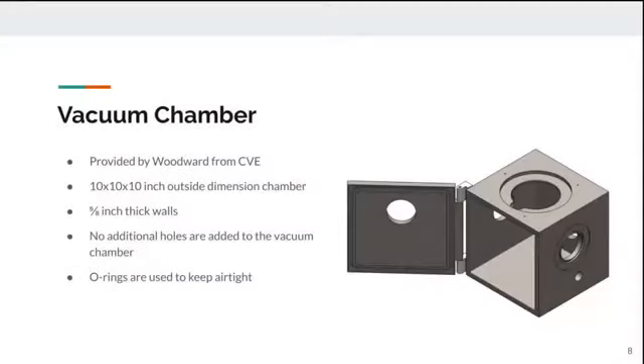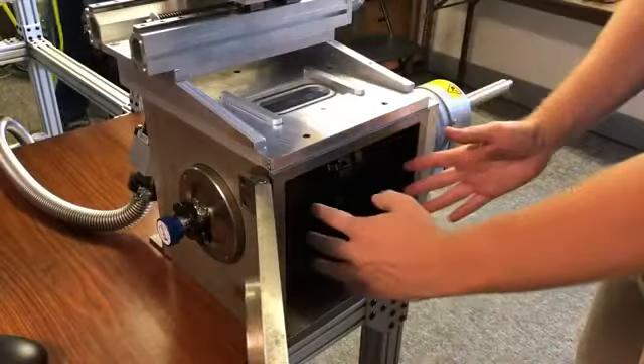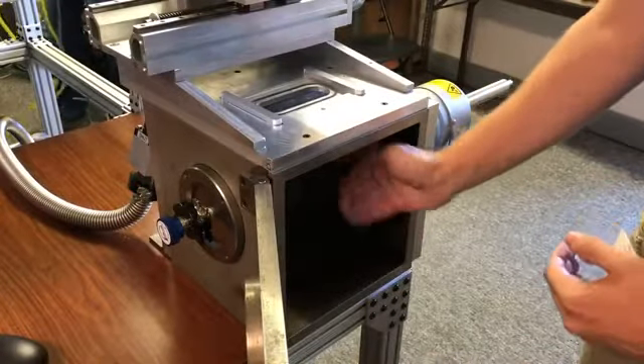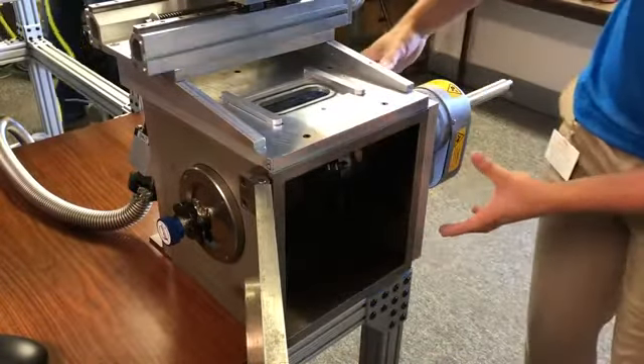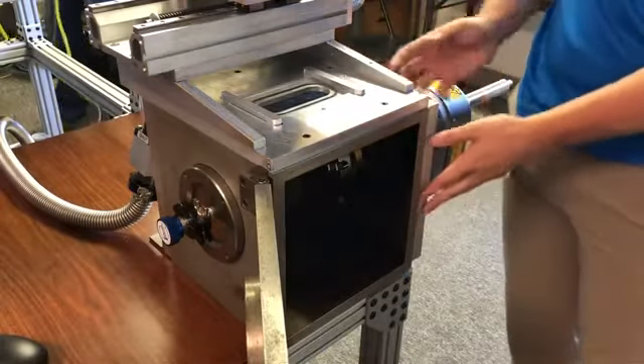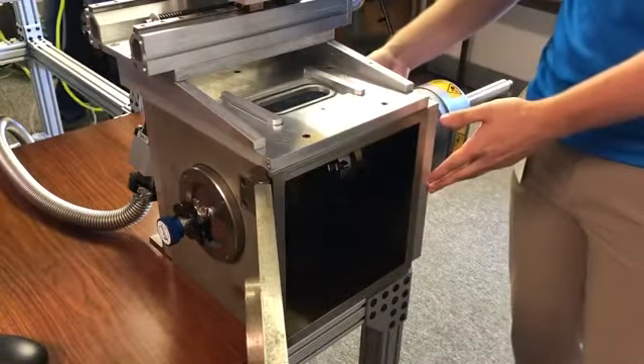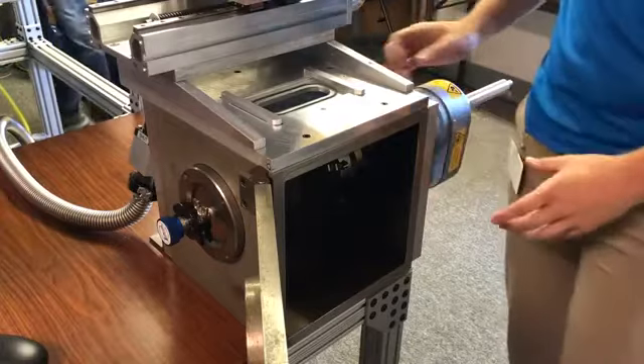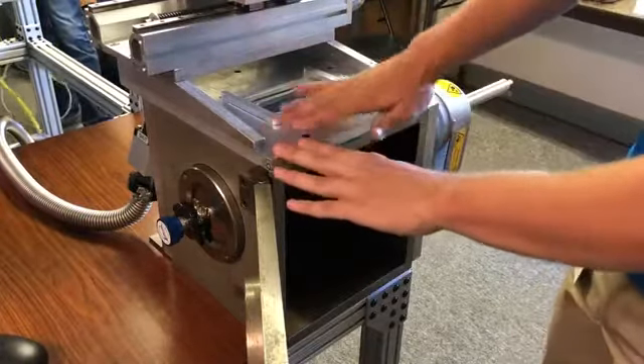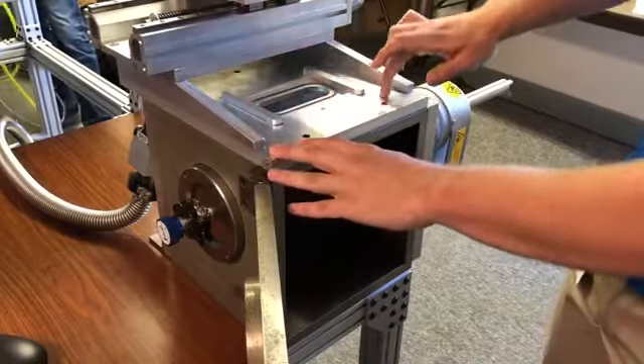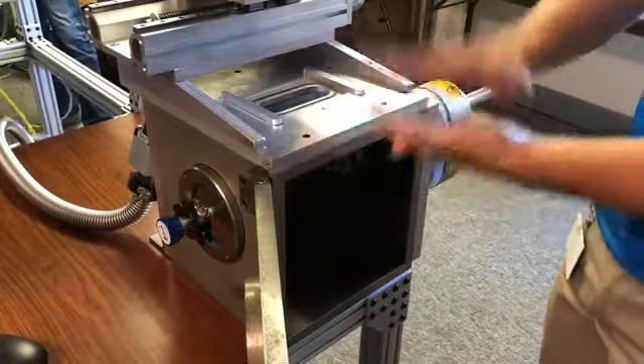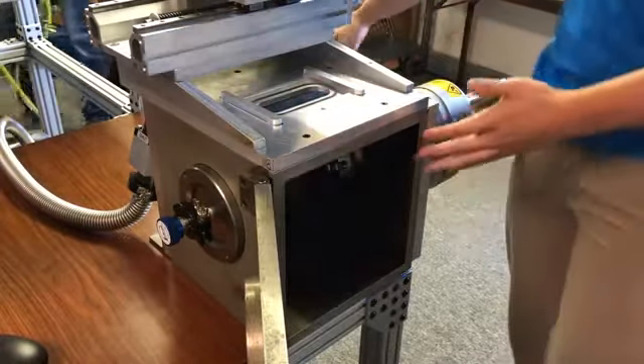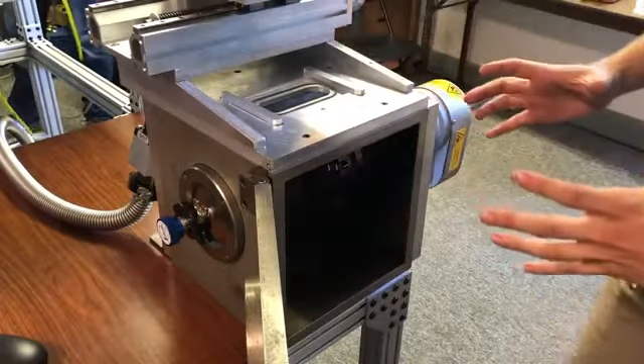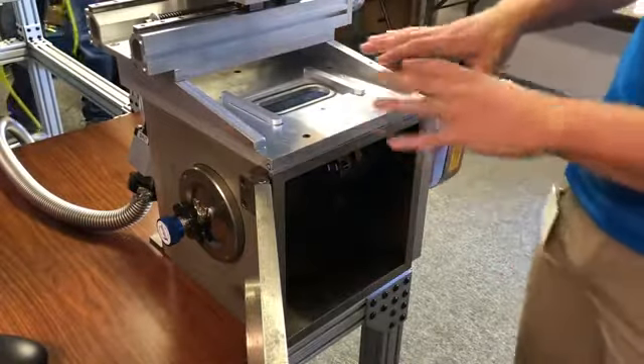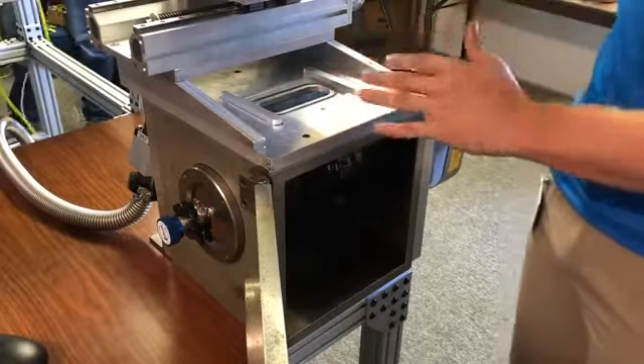This is the vacuum chamber that we'll be using for the project. It's a 10 by 10 inside chamber, and it's 10 inches deep. The rotary comes in the side here and is mounted with this plate that has an O-ring groove with an O-ring to seal against this face. Up here, this plate right here has an O-ring groove right on the bottom surface that connects to the plate and will seal off. And then the same thing with the back. That gives us a complete vacuum seal while allowing us to put this glass in here for the laser.